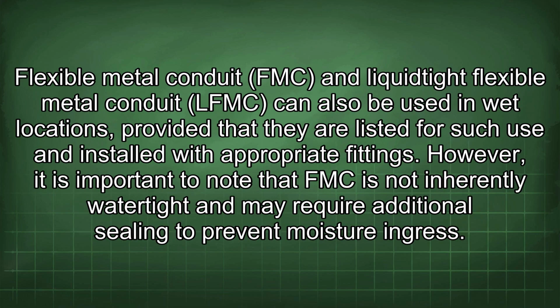Flexible metal conduit (FMC) and liquid-tight flexible metal conduit (LFMC) can also be used in wet locations, provided that they are listed for such use and installed with appropriate fittings. However, it is important to note that FMC is not inherently watertight and may require additional sealing to prevent moisture ingress.